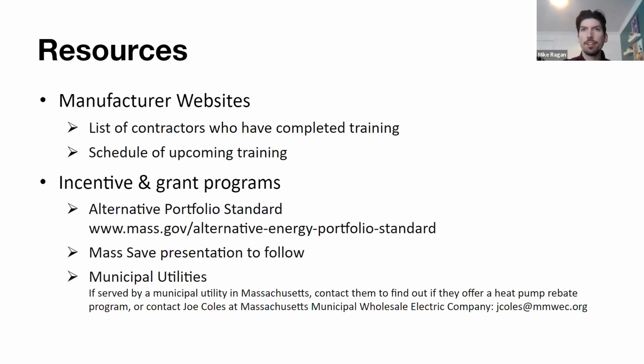Yeah, so every manufacturer is different when it comes to that. I would recommend looking at the respective manufacturer's literature to determine whether the indoor unit type is compatible with an outside air knockout in order to deliver that directly to the space. With cassettes, they have a limit on the number of CFM, I believe about 50 CFM approximately delivered directly to a cassette unit. Anything larger than that, there's actually potential to get a whistling noise within the cassette because you're just delivering way too much fresh air to it.